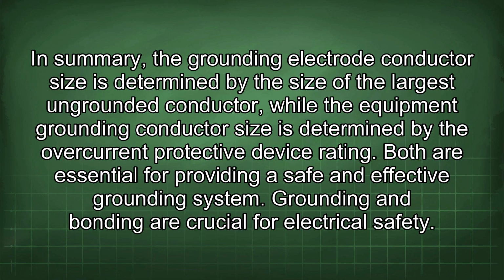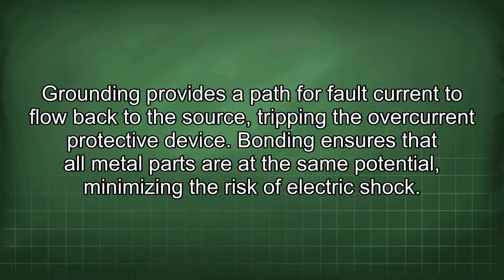In summary, the grounding electrode conductor size is determined by the size of the largest ungrounded conductor, while the equipment grounding conductor size is determined by the overcurrent protective device rating. Both are essential for providing a safe and effective grounding system. Grounding and bonding are crucial for electrical safety. Grounding provides a path for fault current to flow back to the source, tripping the overcurrent protective device. Bonding ensures that all metal parts are at the same potential, minimizing the risk of electric shock.